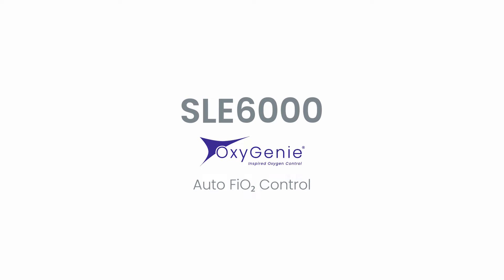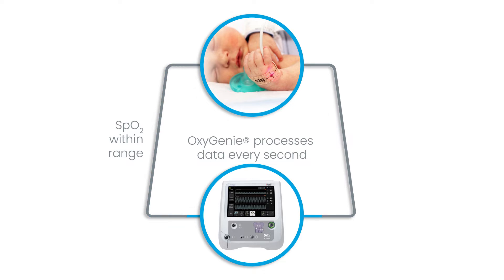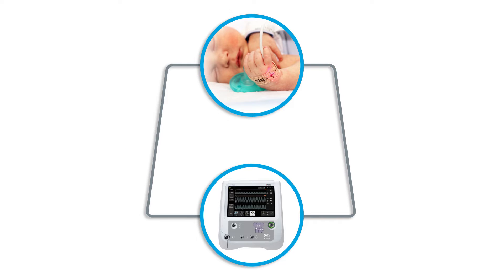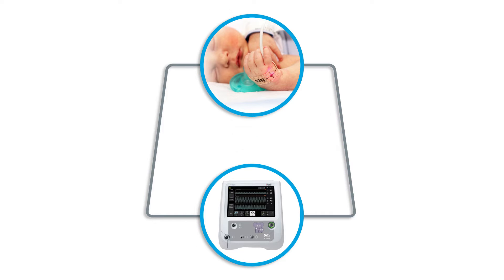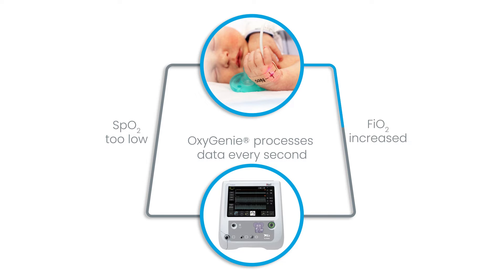Using OxyGenie on the SLE6000. When equipped with OxyGenie and SpO2 monitoring, the SLE6000 enables precise, closed-loop-inspired oxygen control and delivery to the patient in order to maintain their SpO2 measurement in a user-selected target range. This ensures that the patient receives an optimised oxygen level and minimises the risks associated with extended hyperoxemia and hypoxemia.